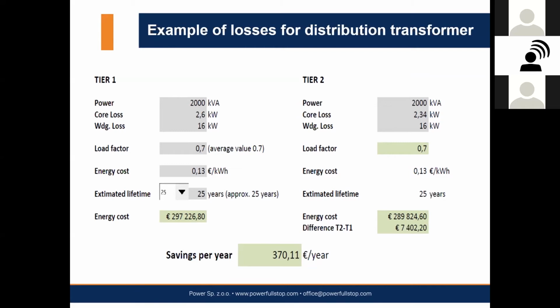I'm considering that a cast resin transformer must work for at least 25 years. This is the minimum, the medium operation time of such a transformer. In that case, just by buying tier 2, we save €370 per year. This is calculated based on Polish energy costs, but of course it changes based on the cost of energy. Some countries are more economic, some countries have much higher costs.